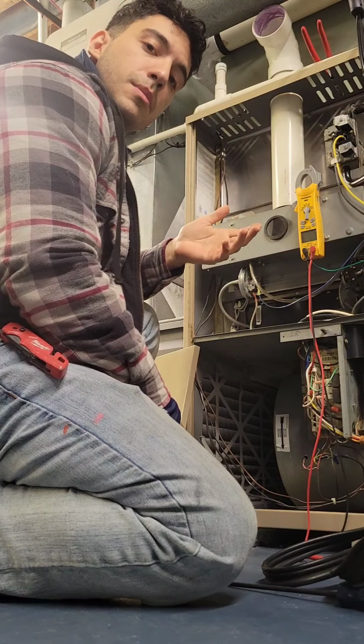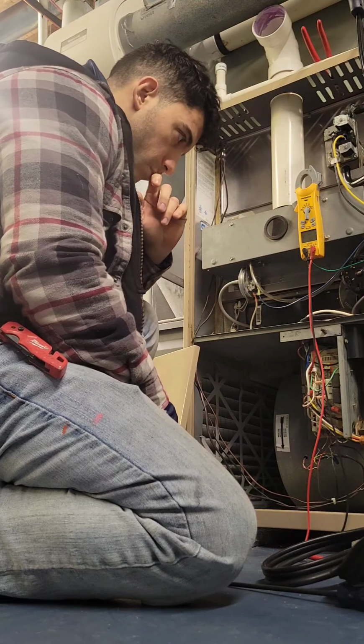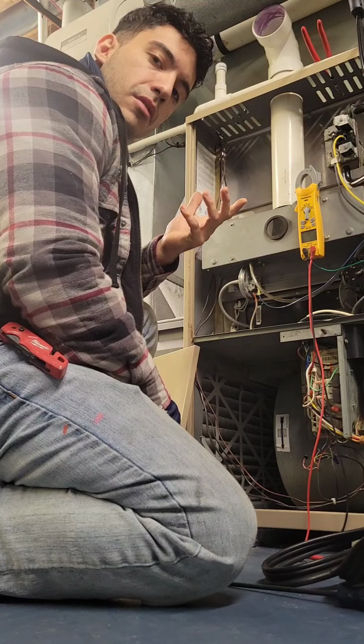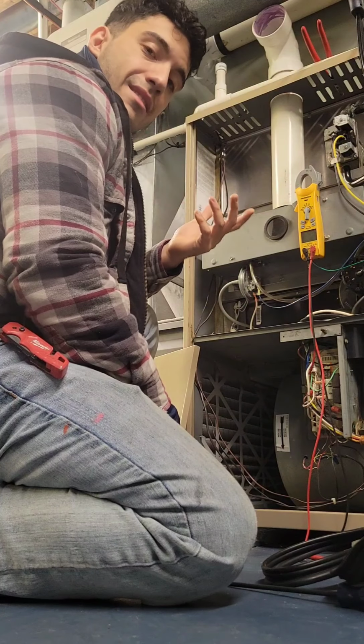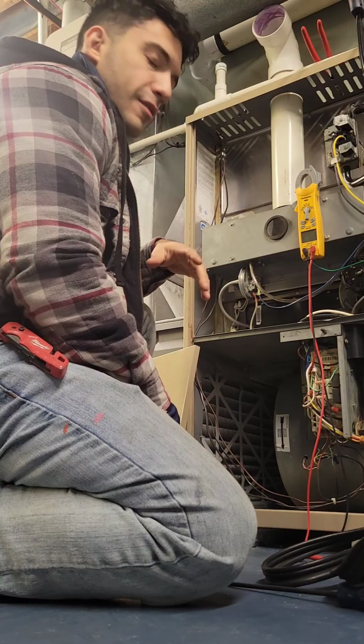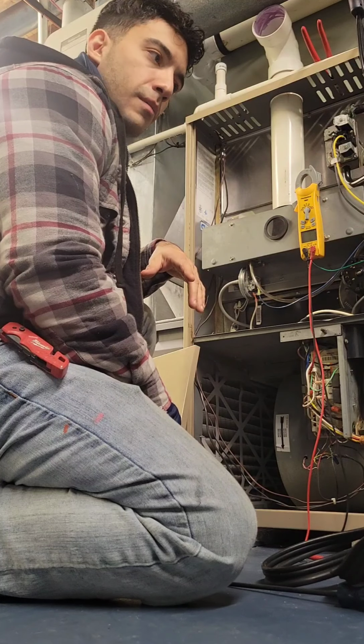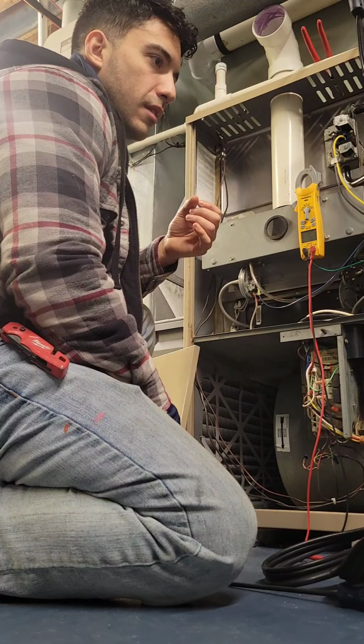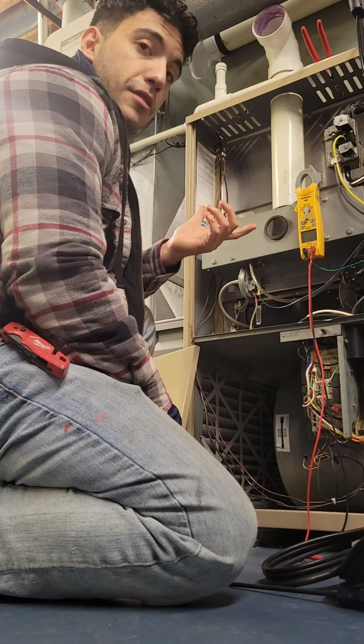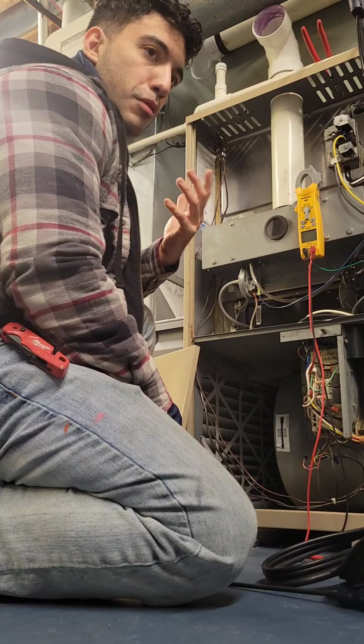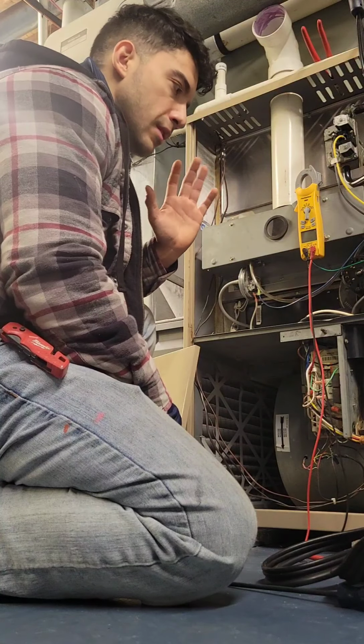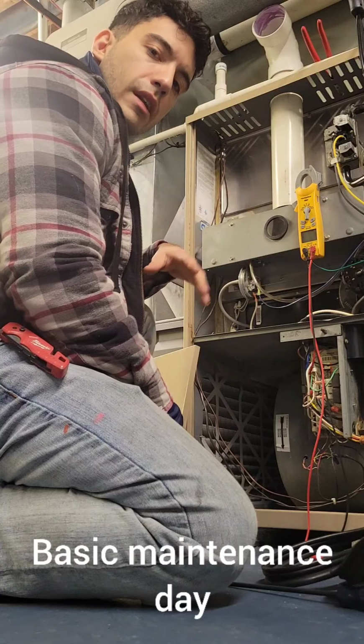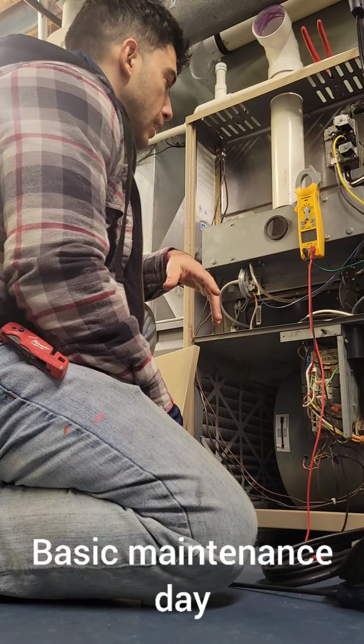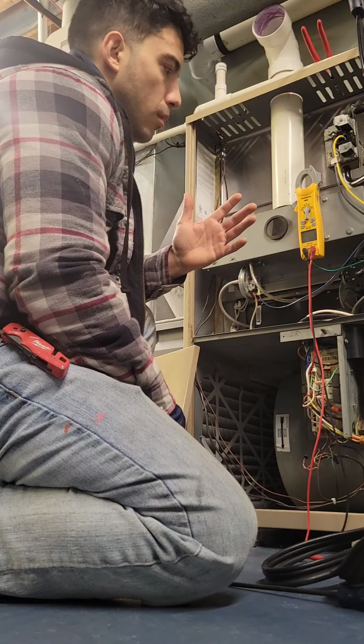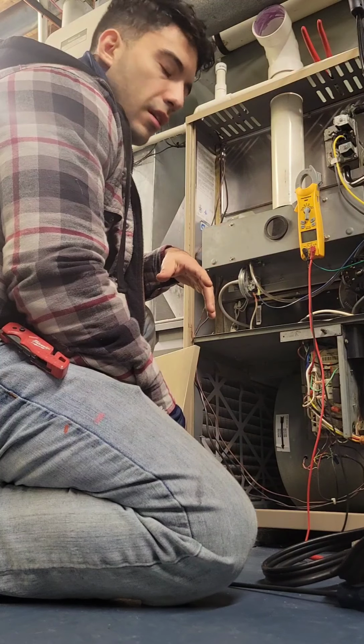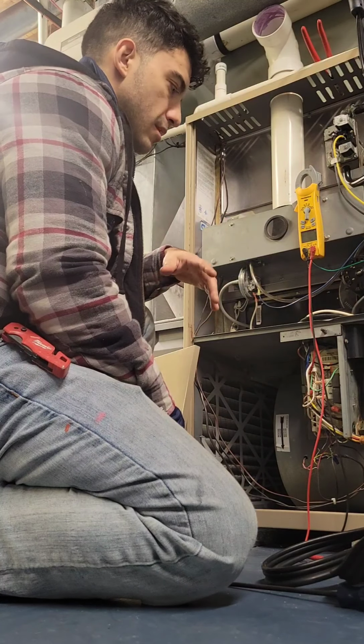If it doesn't go into a chimney, that'll indicate that it's condensing equipment if it has PVC venting to the outside. And condensing equipment typically tends to be on the higher efficiency side because of how it burns the fuels and what it actually does through the combustion process, and that's where you get your efficiency from. So just a couple of things that we checked during the basic heating maintenance. I mean, it's nothing crazy.